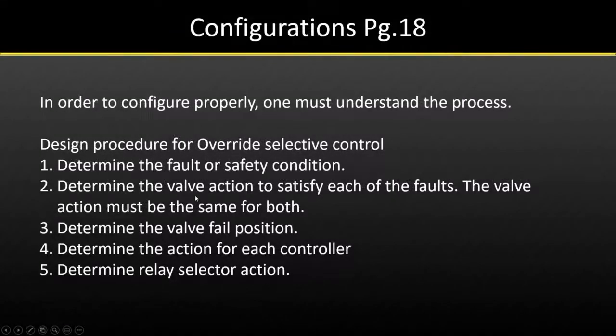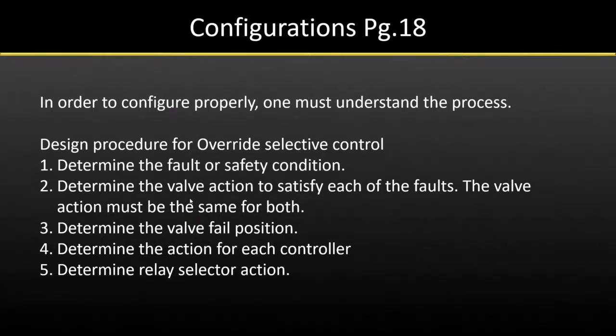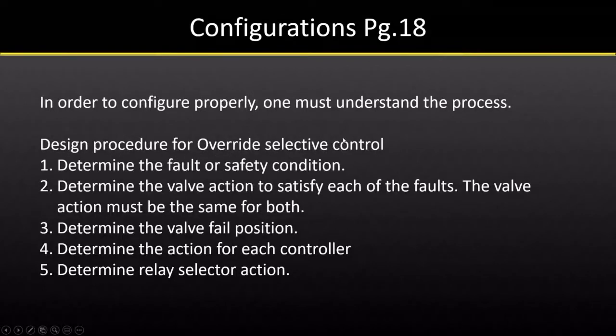So how do you configure one of these? How do you know if it's going to be high select, low select, or median select? There's a process for it. To design the procedure for override selective control — one of the most common ones — the first step is to determine the fault or safety condition, such as what happens if you have too high a line pressure or too low a suction pressure.